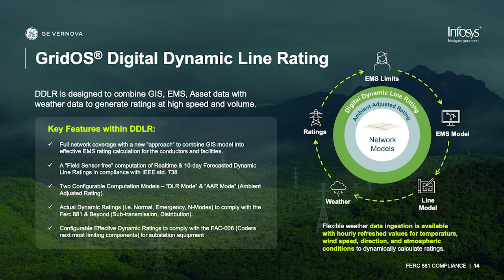The digital DLR is going to combine all of your GIS, EMS, asset data, et cetera, so that you have a much more representative rating set on your transmission equipment that's based on the real-time ambient conditions. For the EMS-based solution, at a minimum, you would use an ambient adjusted rating table, so it's only using the variable of the ambient temperature. So you're getting a small amount of gain over your traditional line ratings.